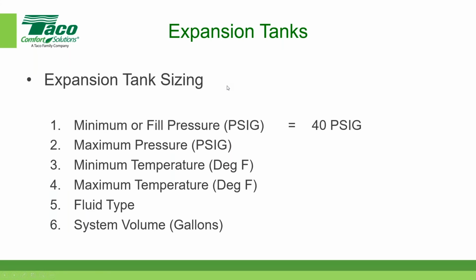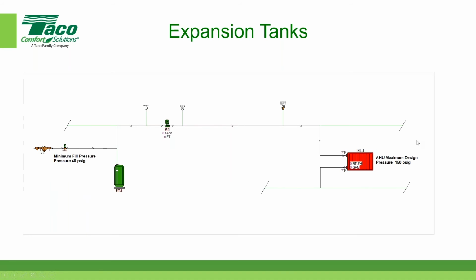So the maximum pressure is a little bit more involved, but it's fairly straightforward. In our example, this is one method for determining the maximum pressure at the expansion tank. There are other methods. They are all similar to this method, but we're going to use this one for today. We're going to assume for a moment that our maximum design pressure for our equipment at the lowest part of the building is 150 pounds per square inch gauge.